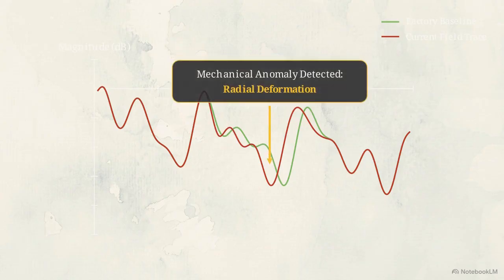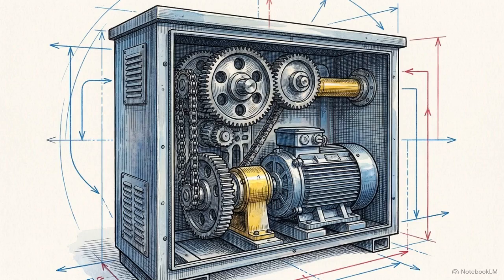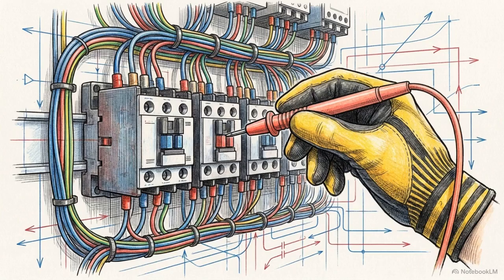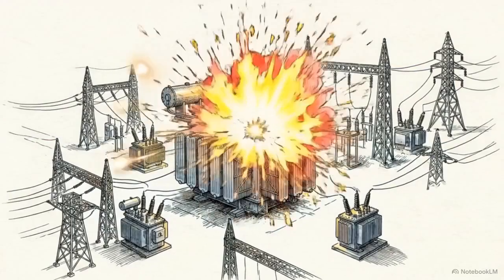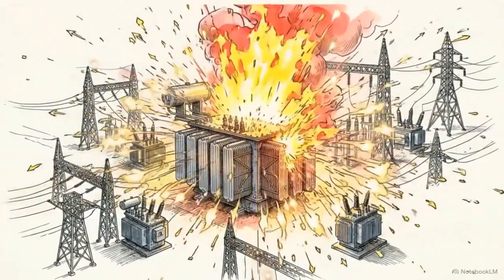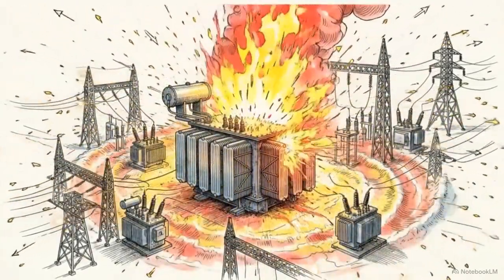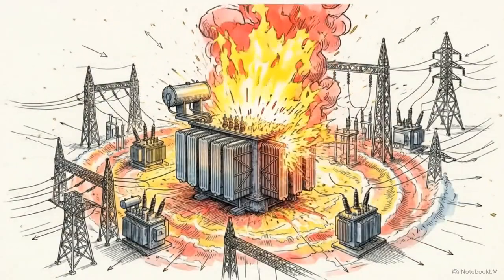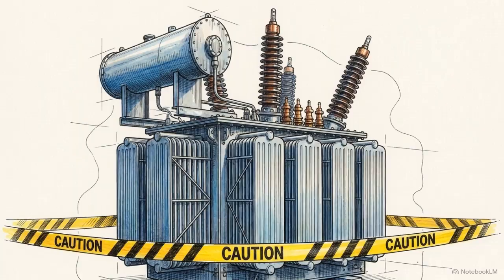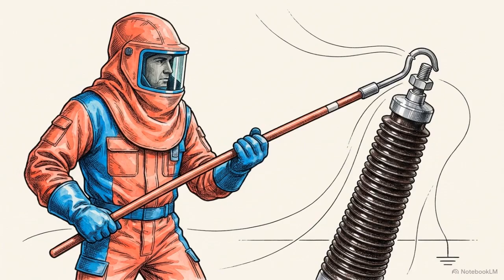For dynamic systems like the on-load tap changer, a motor drive failure or abnormal current signature initiates a troubleshooting path focused on mechanical binding in the diverter switch or logic errors in the contactors. These data anomalies represent the final opportunity to detect a defect before it manifests as a catastrophic multi-million-dollar failure on the live grid. Because of the massive capacitance involved, every high-voltage test requires a mandatory hold point. A witness must visually confirm the safe, complete discharge of stored energy before leads are moved.